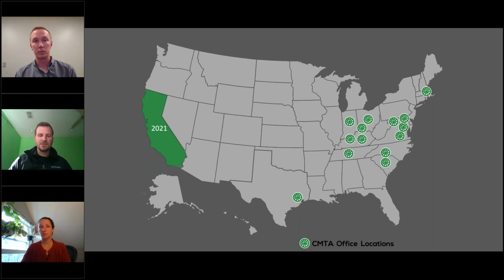In California with the wildfires, it's sadly a bit more predictable than a chemical spill or something like that. I think filtration is the answer. That's another positive side effect of the coronavirus situation—we're seeing higher levels of filtration being used at DOAS units, but also at zones on heat pumps. Ultimately, we're looking at running some of those zones in fan-only mode when not calling for heating and cooling, so it acts essentially as an air purifier for the space. Those filters are a little more expensive, but unfortunately that's probably the answer for the near future.